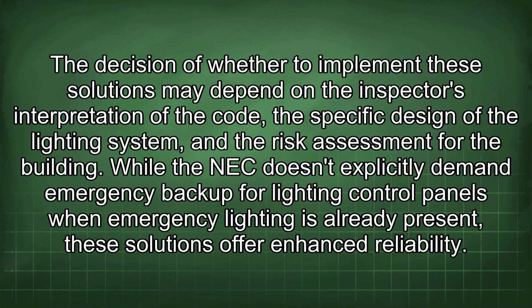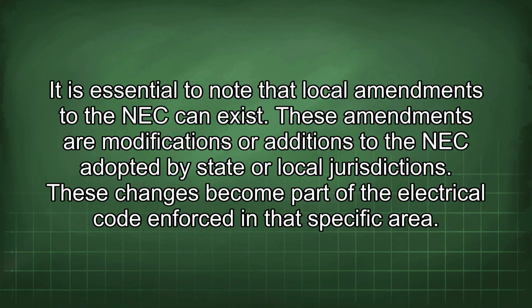The decision of whether to implement these solutions may depend on the inspector's interpretation of the code, the specific design of the lighting system, and the risk assessment for the building. While the NEC doesn't explicitly demand emergency backup for lighting control panels when emergency lighting is already present, these solutions offer enhanced reliability. It is essential to note that local amendments to the NEC can exist.